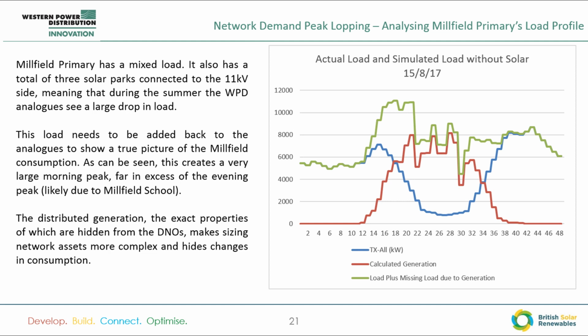Now there are quite a few large peaks and troughs that are very sudden, and I suspect that's an artifact of trying to extrapolate 3 parks' worth of data from one, so you can smooth those out. And I believe the large morning peak could be from the very large school that's attached to the primary. When they're starting up at the beginning of the day, they have much larger loads. It demonstrates that it's quite difficult for a DNO to find out what load is being put on their system, because they don't have visibility of the generation.